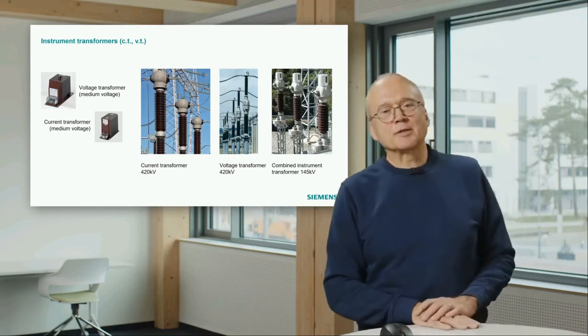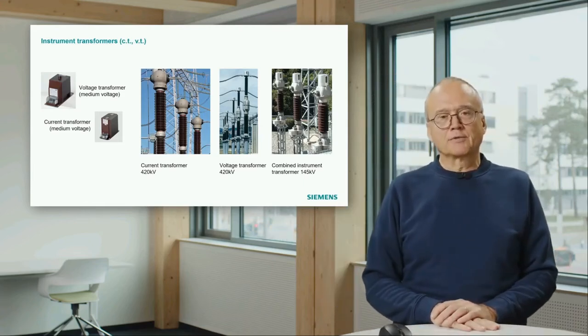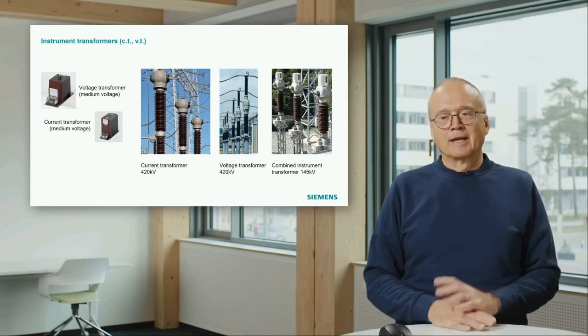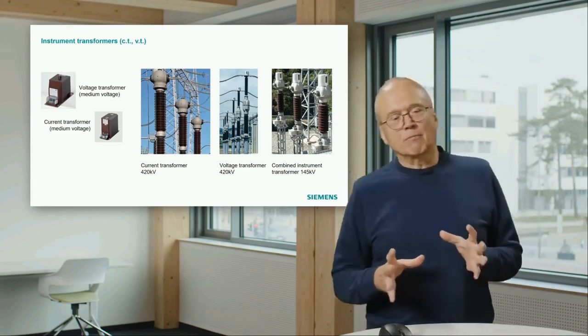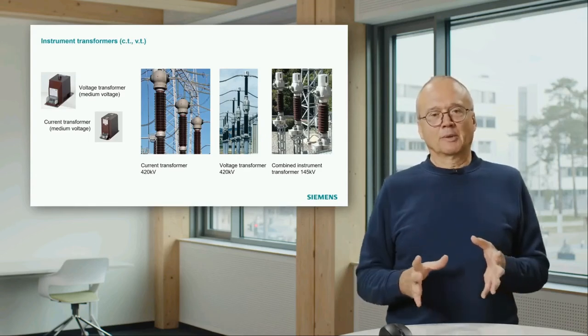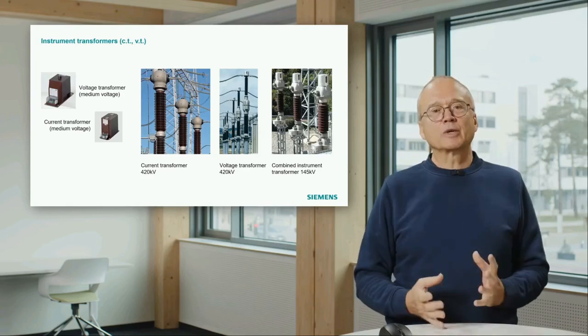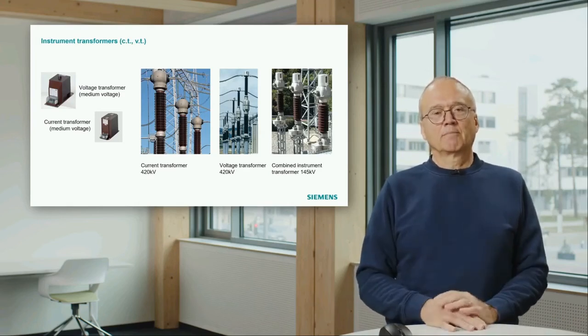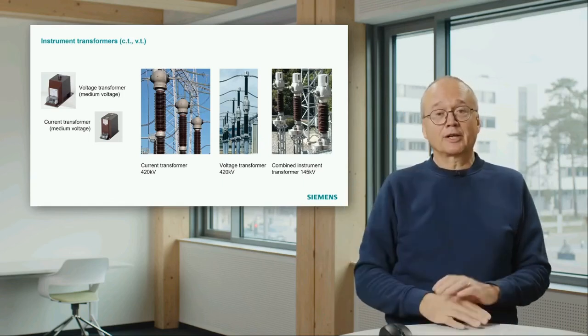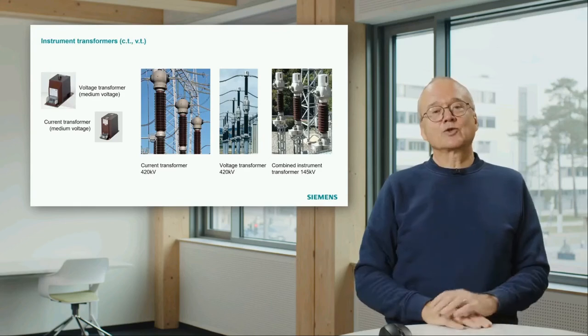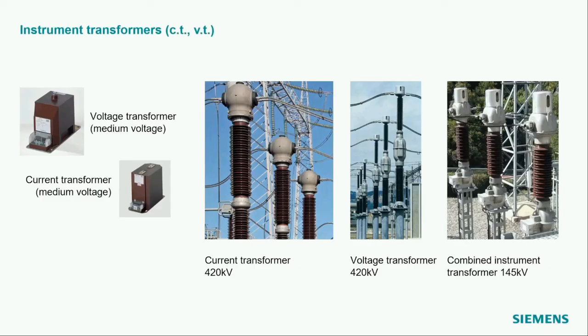On the right-hand side, we see the same story for the higher voltage levels, in this case 400 kilovolt. In this case, you don't need more power in the current transformer and the voltage transformer. These things are just bigger because we need more insulation. Because we have to measure a voltage on a 400 kV level and need insulation for 400 kV. You see a current transformer for 400 kV. The current flow is here through the top of this thing. We also see a voltage transformer where the voltage is connected and our protection relay is connected somewhere down there.